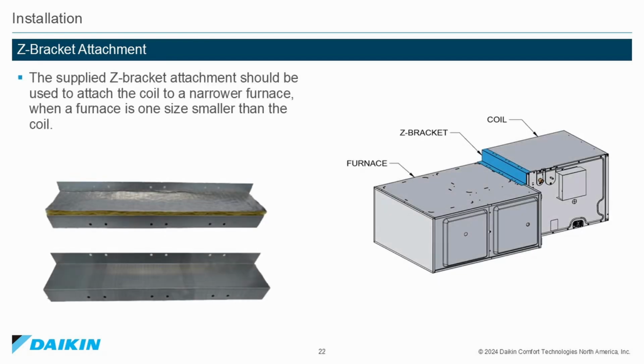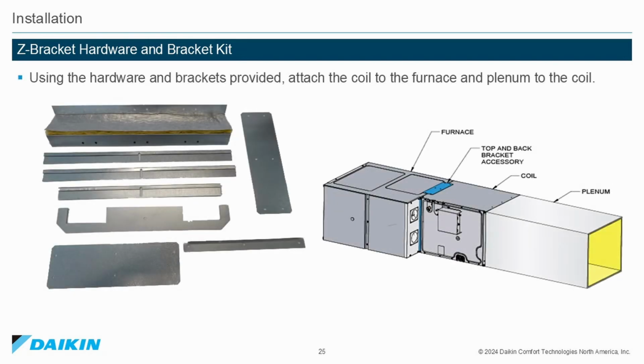Z-bracket attachment. The supplied Z-bracket attachment should be used to attach the coil to a narrower furnace when the furnace is one size smaller than the coil. For example, if the coil is 21 inches and the furnace is 17.5 inches. Z-bracket hardware and bracket kit. Using the hardware and brackets provided, attach the coil to the furnace and the plenum to the coil.